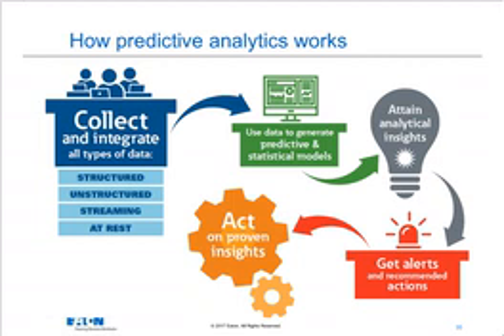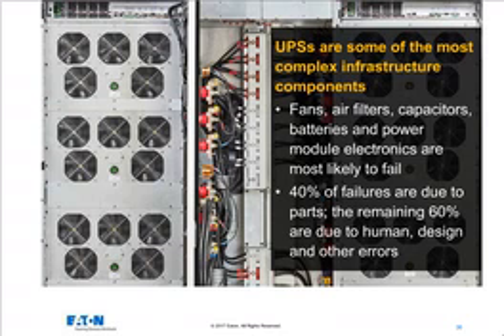If I have a UPS, for example, that's had a temperature rise of X degrees C over a certain period of time, I can compare that with other UPSs in the field to say if I see a temperature rise on this bus bar at this ambient temperature rate in this period of time and compare that with 400 other UPSs, I can get a good idea if I'm actually seeing a connection that's working loose or a normal temperature rise under load change and that type of thing. So we get the alerts out to the user, but we act on those insights and eventually automatically so that we can provide prior or predictive information on what is likely to happen to the UPS.